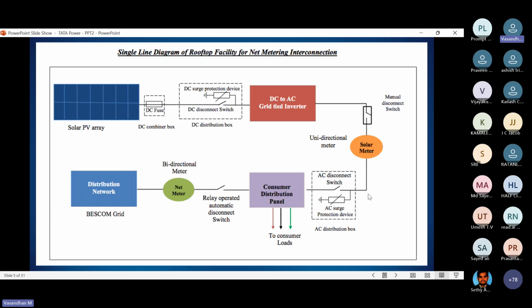This is our inverter, connected to the solar meter, and again it goes to the AC-DB, which is the AC distribution box connected to that load. After that, there is one relay switch, then a bidirectional meter for net metering, sending it to the Bescom grid. So as per this diagram, this is our overall single line diagram for rooftop models.